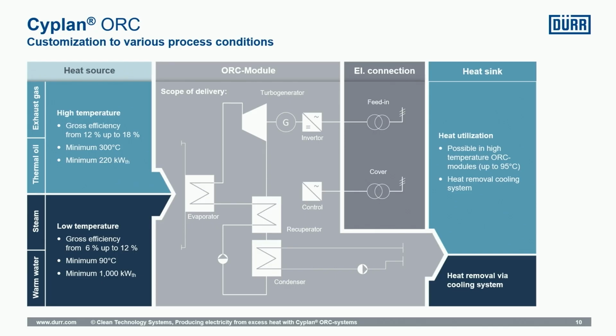When we have high temperature input from thermal oil and/or flue gas, it's a different game. You can do electricity only, condensing completely and giving that heat to the cooling tower. Or, as another option, we run the condenser at higher temperatures, in the range of 80 to 90 degrees C, or about 150 to 200 Fahrenheit. This heat is quite significant, as it can be up to 80% of what was put in on the heat source side, and it can be provided at the condenser as secondary heat for subsequent purposes, which I'll explain soon.